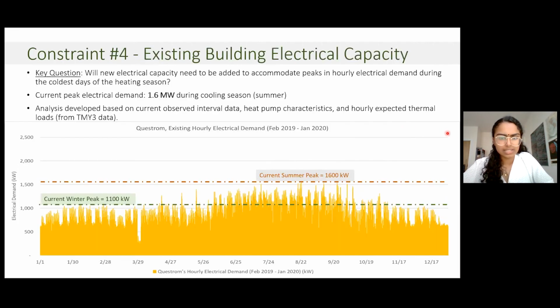The last constraint to consider is the impact of electrification on increased building electrical capacity. Our question here was, will new electrical capacity have to be added in order to accommodate peaks in our hourly electrical demand during the coldest days of the heating season? The way that we were able to analyze this is by looking at our current cooling season peak demand, which is 1.6 megawatts, and looking at our current heating season demand, which is 1.1 megawatts.